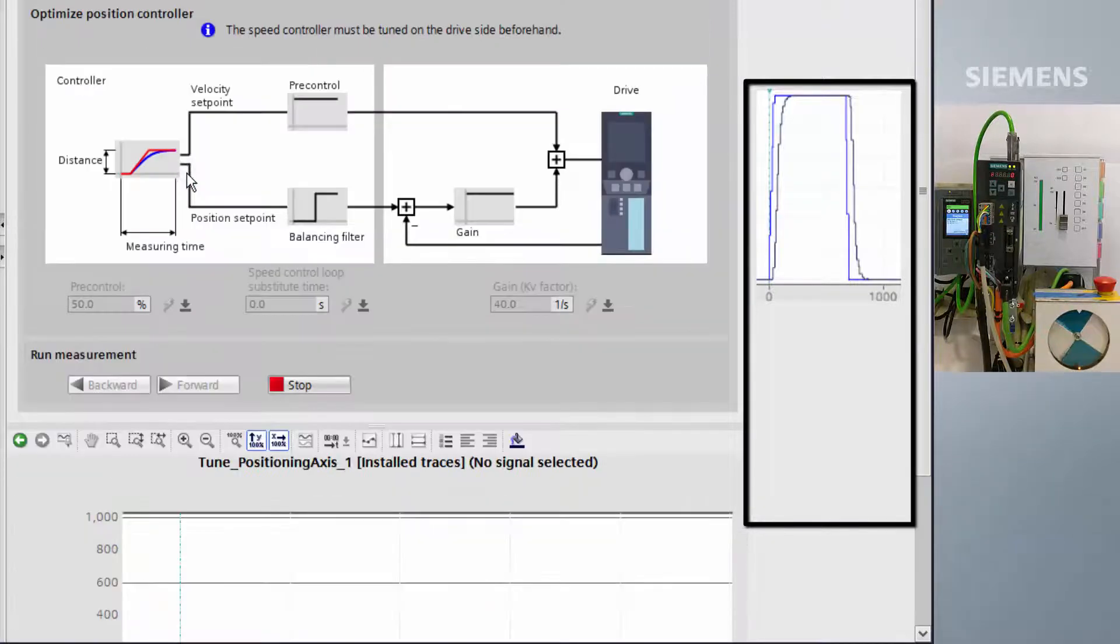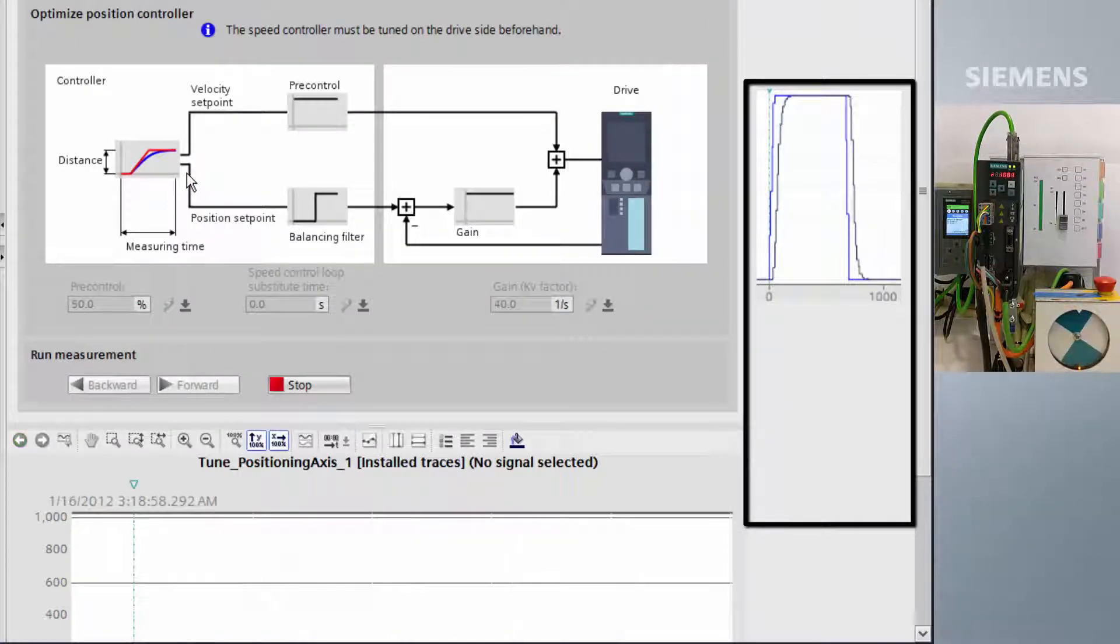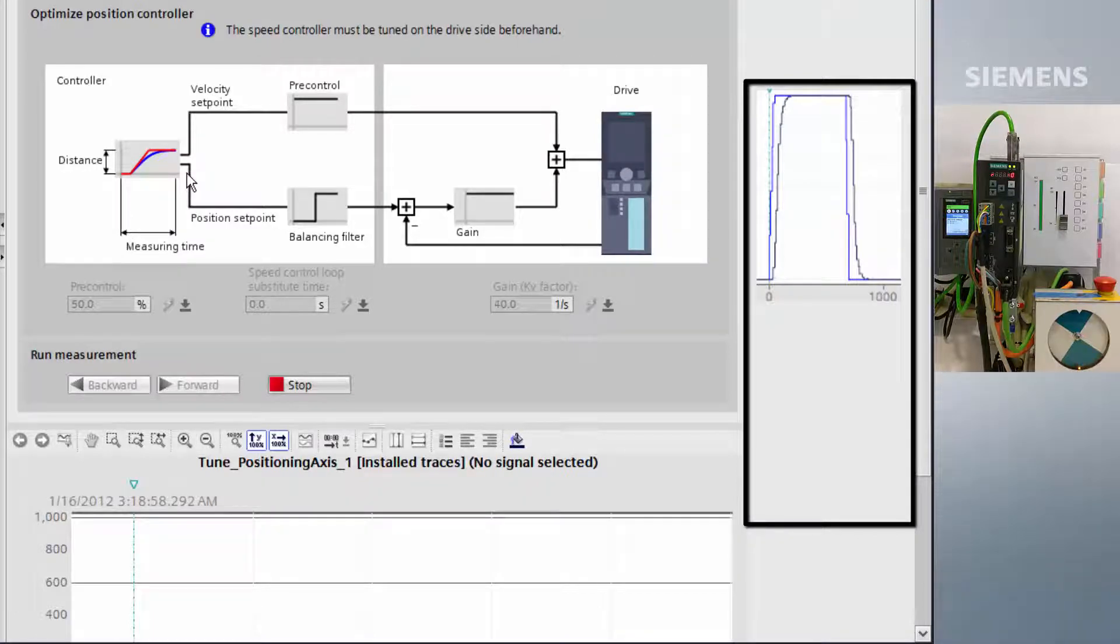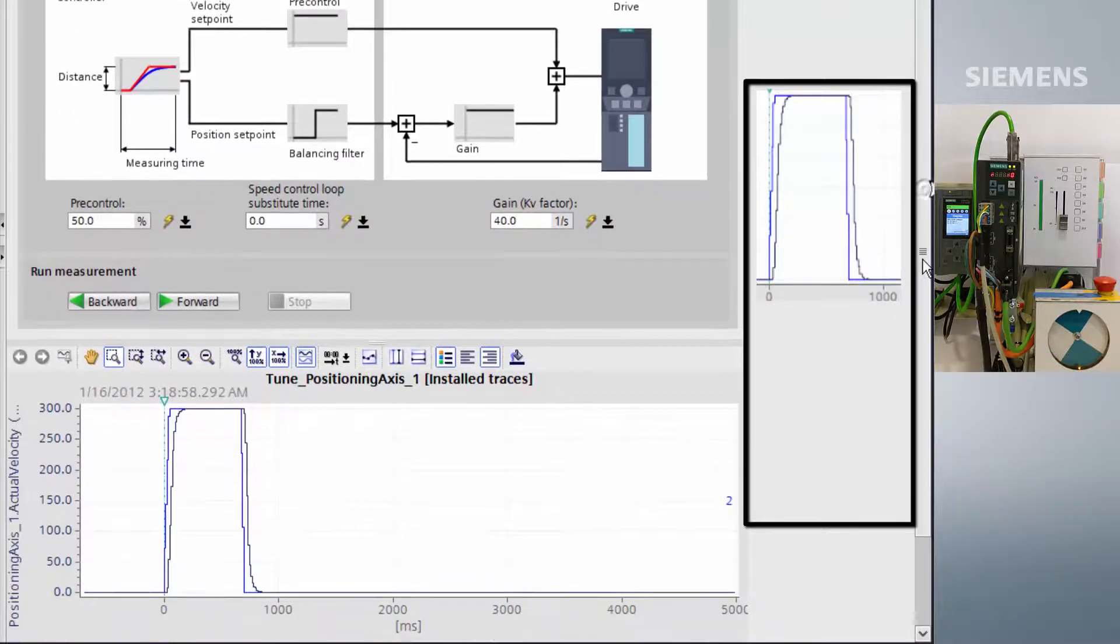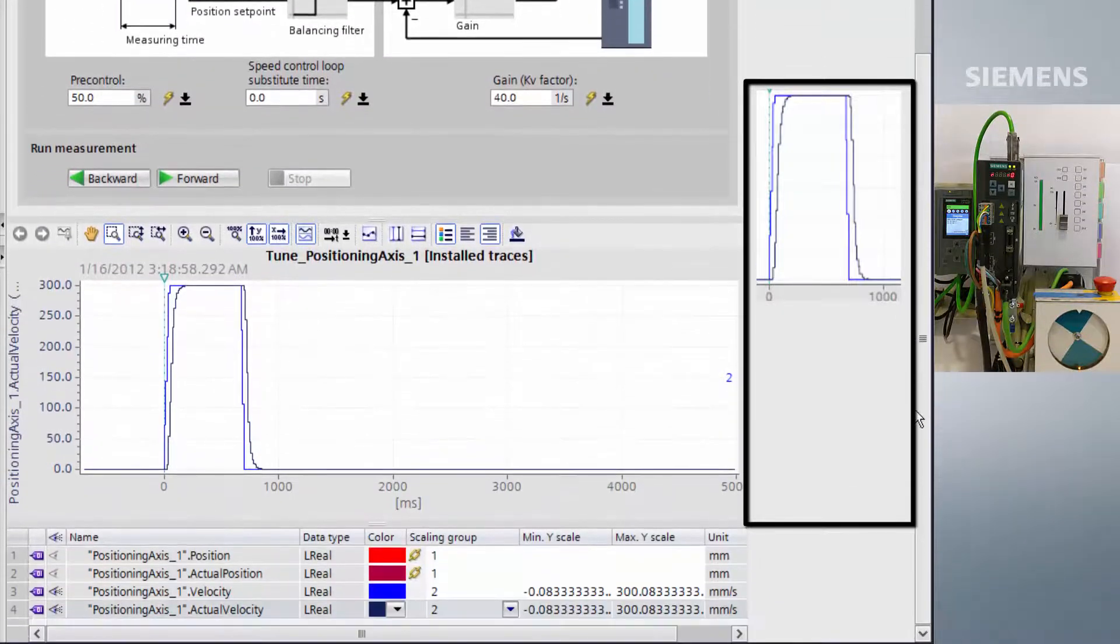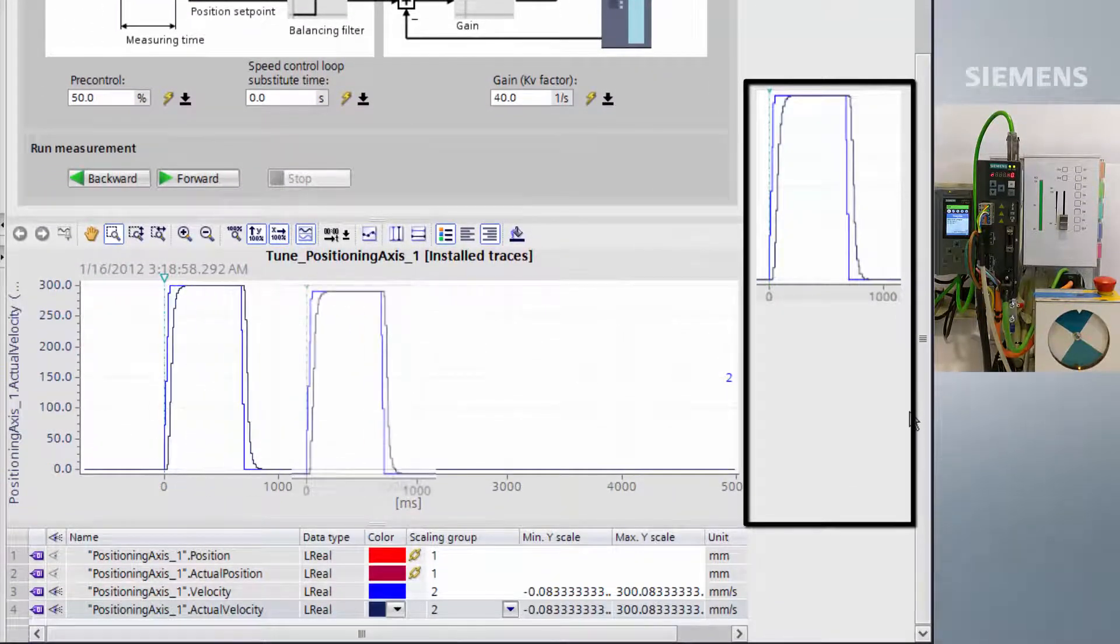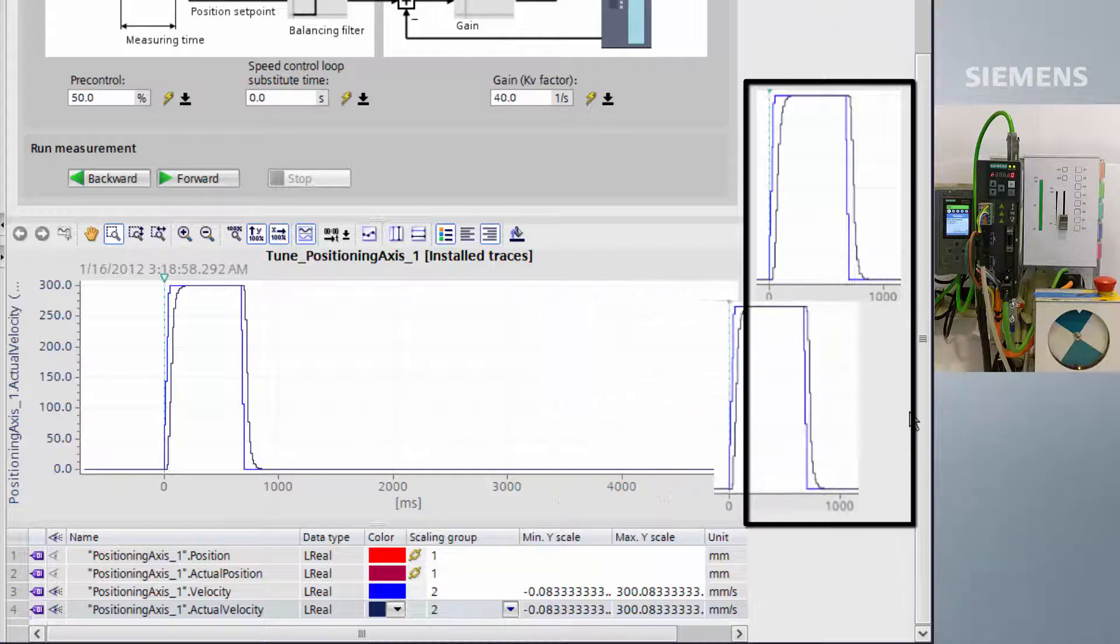If the system contains, for example, mechanical stiffness, uneven loads, or high inertia, which the pre-control cannot account for, then it must be set much lower as more feedback measurements are required to accurately control the system's movement.